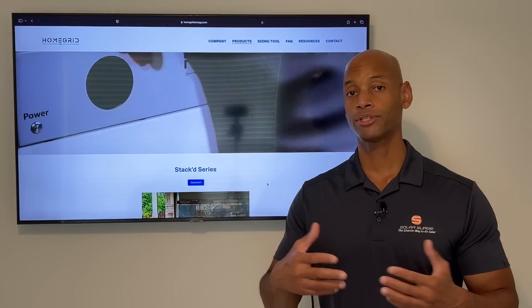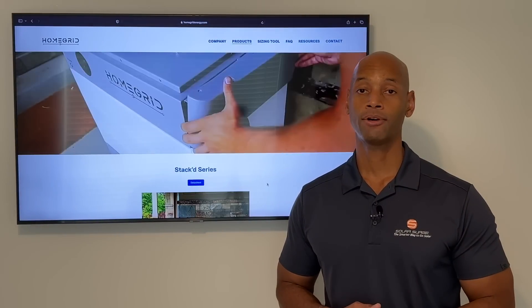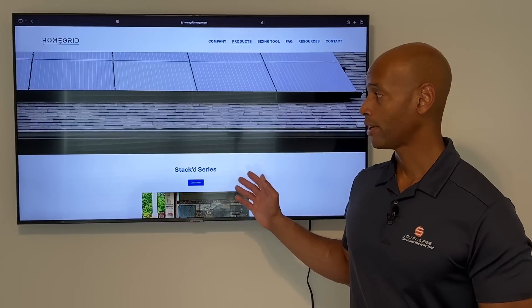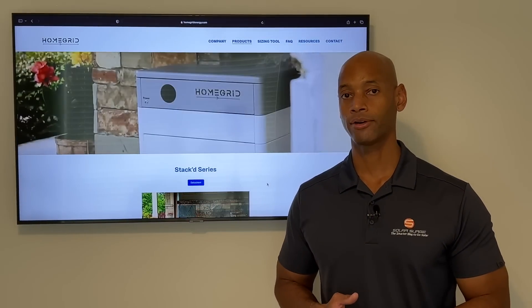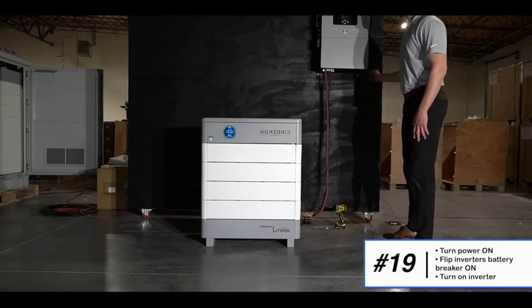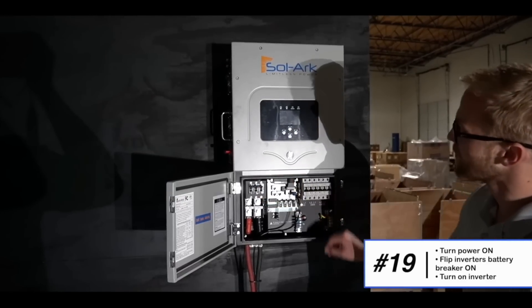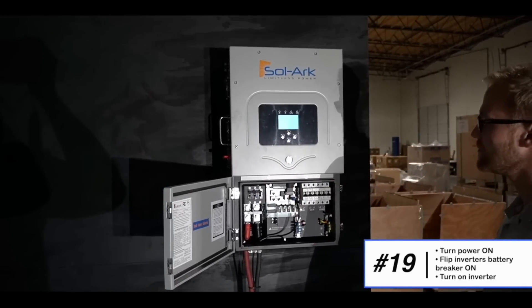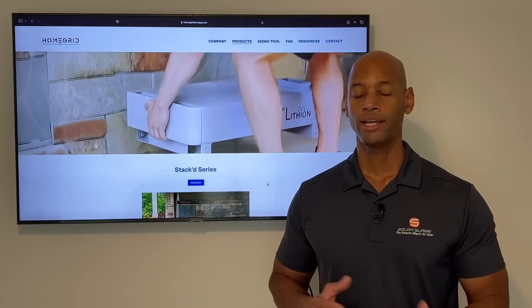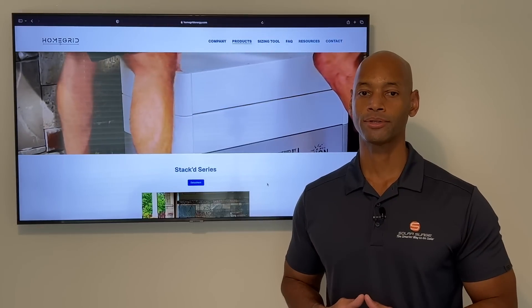In terms of how it presents itself to other components in the system, it is a 48-volt nominal battery. So you're going to have to pair this battery with a 48-volt hybrid inverter — whether that's a Sol-Ark, maybe a Schneider Electric, a Xantrex XW Pro, or an Outback Radian type inverter. The battery is providing storage only; you'll still need a separate inverter to handle inversion, rectification, and switching between different power sources.